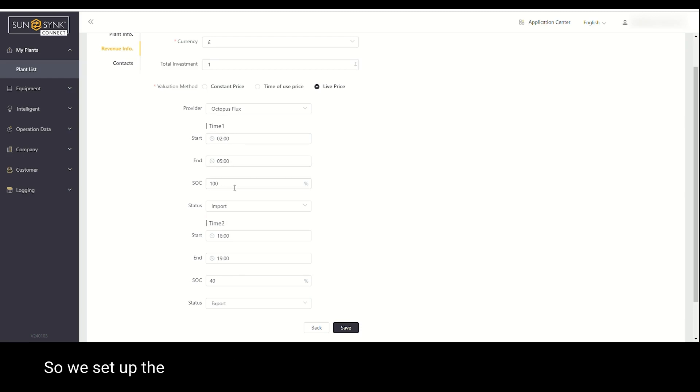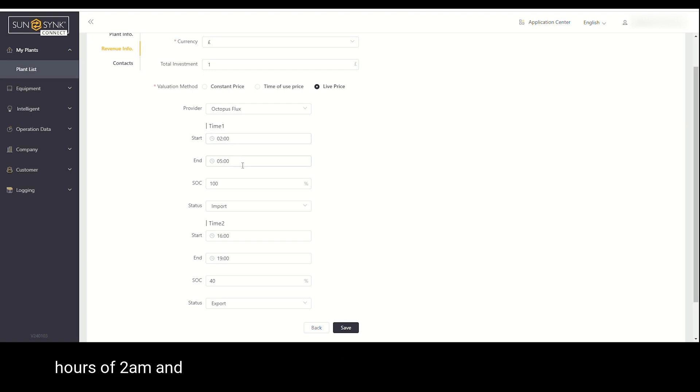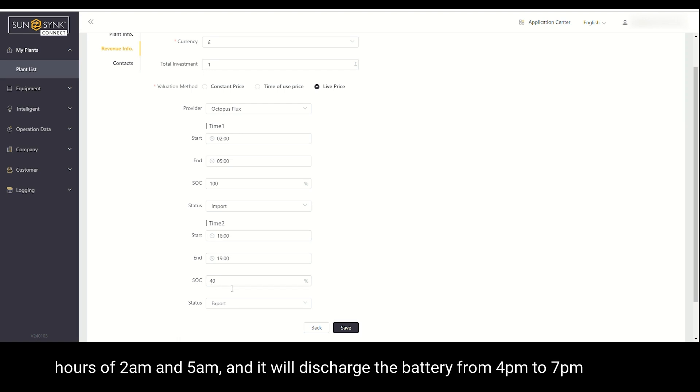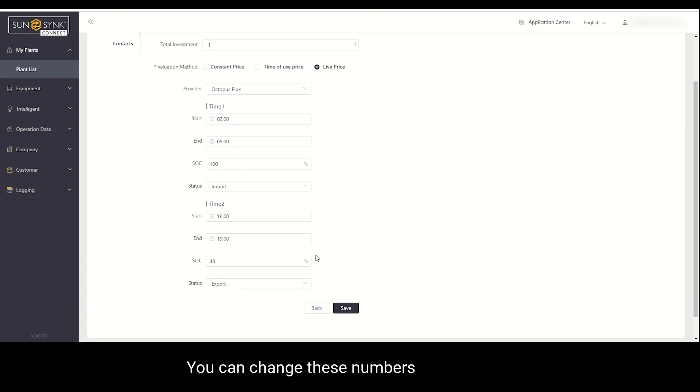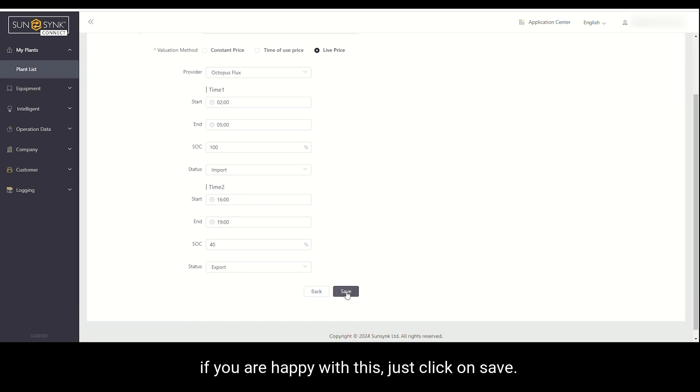So we set up the imports that will fill the batteries up to a hundred percent between the hours of 2am and 5am, and it will discharge the battery from 4pm to 7pm up to 40%. You can change these numbers if you'd like, but if you are happy with this, just click on save and that's it.